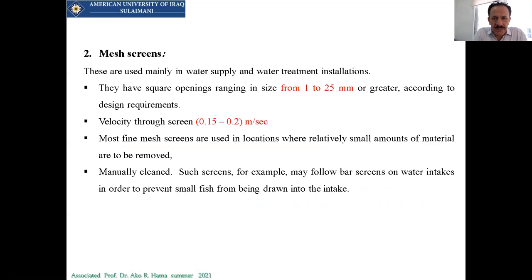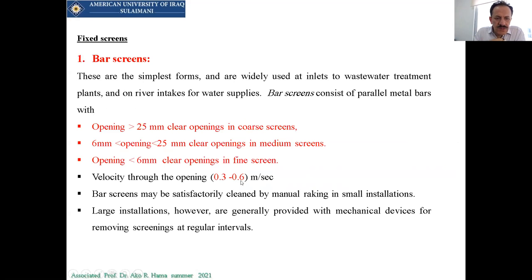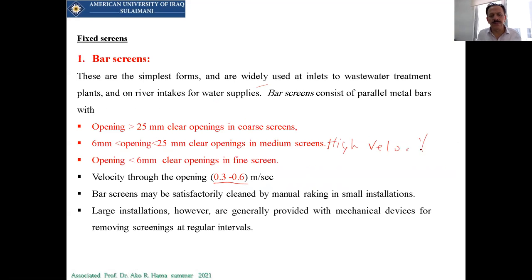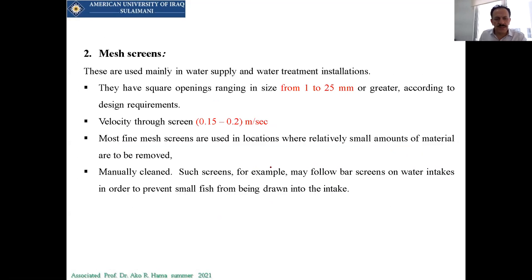Then there is a mesh screen, which looks like cross bars, with openings between 1 to 25 millimeters. The main point is that we have to know the velocities between the bars — high velocity is not allowed. It should usually be from 0.3 to 0.6 m/s for bar screens and 0.15 to 0.2 meters per second for mesh screens. We need this to check the spacing between the parts.